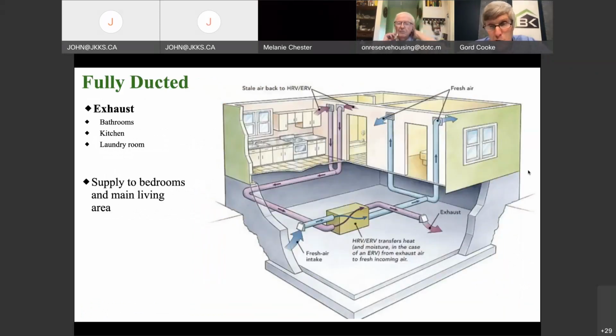If you don't have forced air heating, if you have electric baseboard, for example, or radiant heat, then you would exhaust from bathrooms and kitchens and you would duct the fresh air directly to the bedrooms and main living areas. It doesn't have to go to every room. The codes would say to bedrooms, 1 to each bedroom and 1 to the main living area. This also helps with that wood stove scenario or central heat pump because it allows you to distribute air around the house. So there's air movement between the rooms and that helps distribute the heat as well.